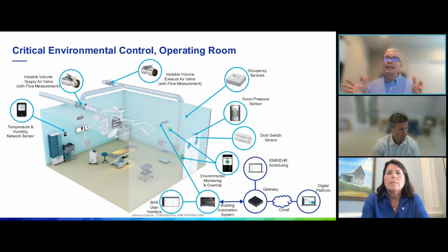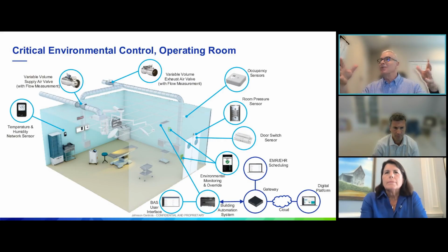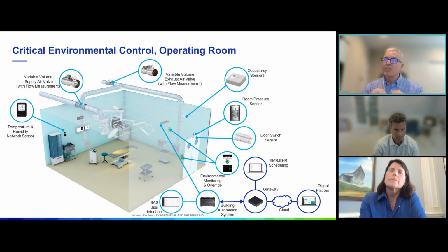And then ideally what we want to happen is that air then goes and captures all those contaminants or anything that's dangerous within that space, and then efficiently flushes it out to those vents that we see on the walls, on the far wall to the right and to the left, and exhausts it out of that space. And that's what we mean by ventilation effectiveness, because what we find in a lot of these spaces is that we're concerned about not meeting compliance. So we're, what we say, quote unquote, overperforming.